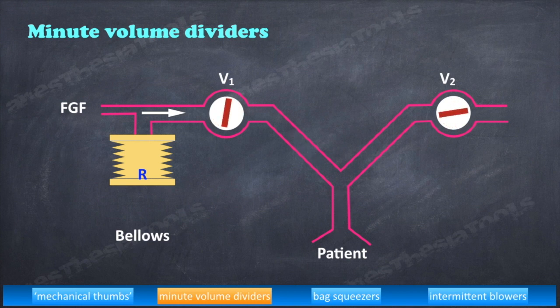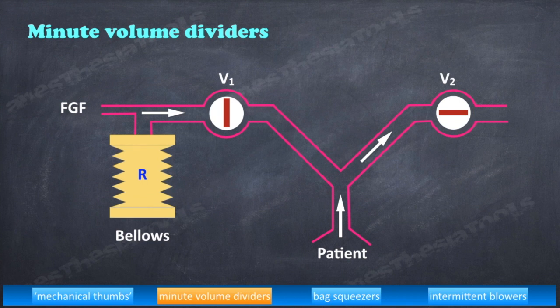When V1 closes, V2 opens and exhalation is permitted, allowing the reservoir bag to refill in preparation for the next breath. It may be noted that all of the driving gas that is supplied is delivered to the patient. These ventilators are referred to as minute volume dividers as they merely divide up the intended minute volume supplied by the driving gas. The most common type used was the series of ventilators designed by Dr. Roger Manley.